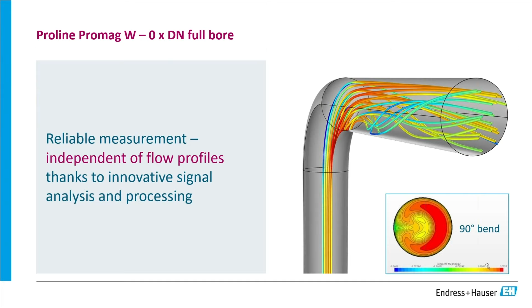So what it looks like if you look in this picture above, whenever it comes around a bend, the flow profile is kind of all jumbled in the straight section right after an elbow. So for example, a 10-inch line size flow meter would require 50 inches of straight pipe ahead of it, or a 20-inch line size meter would require 100 inches. So as you get into larger line sizes, it becomes more challenging to install a mag meter to get a good, accurate flow reading. So if you want to click on the next slide.